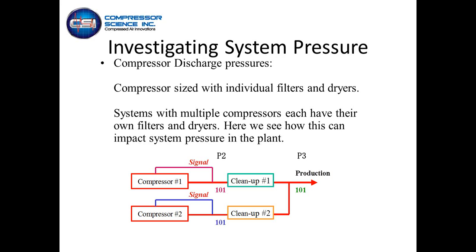So what you're not taking into consideration is that you've got a dryer and you've got filters in the compressed air system that are now dealing with pressure differential across those filters. So your pre-filter and after filter on the one dryer could be running at a 5 or 6 pound differential. Your pre-filter and after filter on the other dryer could be running at a 10 to 12 pound differential. So now you've got compressors that are designed to put out 101 or 102 psi that now have to run at a higher pressure in order to overcome that pressure loss through the air treatment equipment.